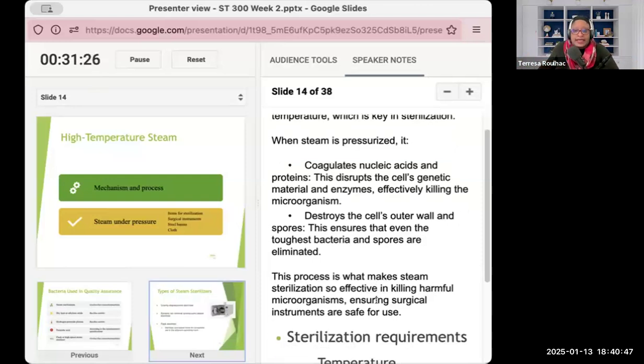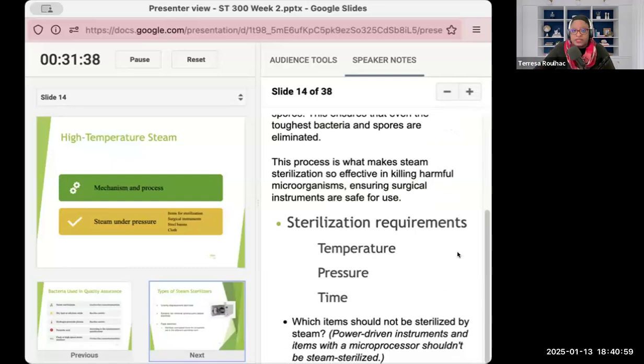It makes the process so effective in killing harmful microorganisms. And that really is important for us when we talk about our surgical instruments being safe for use. So, requirements: temperature, pressure, time. Those are the requirements: temperature, pressure, and time. So, question: how many requirements are needed for sterilization? Well, 3. If you see temperature, pressure, time, and air, well, air is going to be a process of elimination, because temperature, pressure, and time.